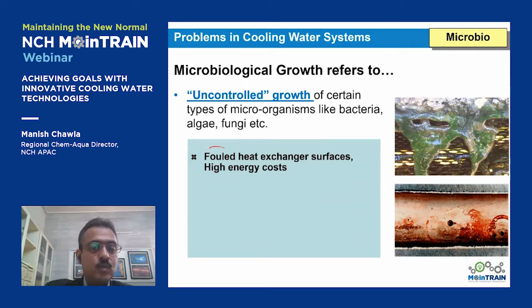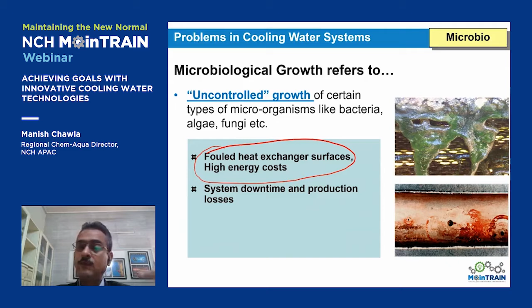So what does it lead to? It can lead to heat transfer efficiency loss, because the thermal conductivity of a biofilm or microbiological slime is even less than that of scale—so it stops heat transfer even more, leading to higher energy cost. We might have to take shutdowns, clean the heat exchangers—high maintenance cost because of leakages like this. See here, this is a leakage because of microbiological fouling. And then we can have problems like Legionella—human health problems.